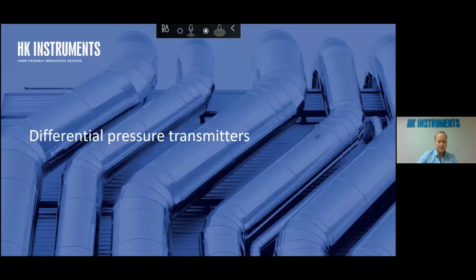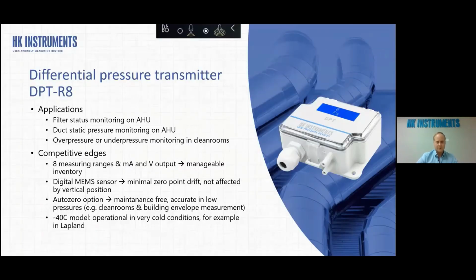So then we can go closer to the individual products. First we go through the differential pressure transmitters we have. First we have the DPTR8, which is the most popular and versatile DP transmitter we have in our portfolio. The basic applications are the filter status on the unit and also the duct static pressure monitoring on the air handling unit. And also you can use it for clean rooms for over or under pressure monitoring.